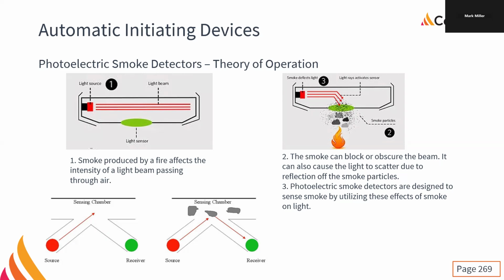Now they have figured out how to avoid false alarms. The light emitter and receiver on a photoelectric type smoke detector are hidden behind a lot of baffles, so just shining a bright flashlight at it is not going to set it off. And the light emitter is not just sending out a steady beam of light; it's a pulsed beam. It's been coded so that we can reduce false alarms. The receiver needs to get that same code of the blinky blinks, and then it's going to work properly.